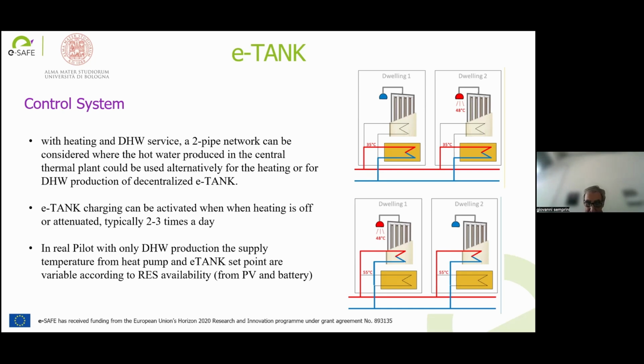For example, when the heating system has underfloor heating, it's possible to modify the temperature of the main system from a higher temperature, 55, 60 degrees, when we have to charge the domestic hot water, to a lower temperature when we have to proceed with heating with the radiating system operating at a very low temperature.